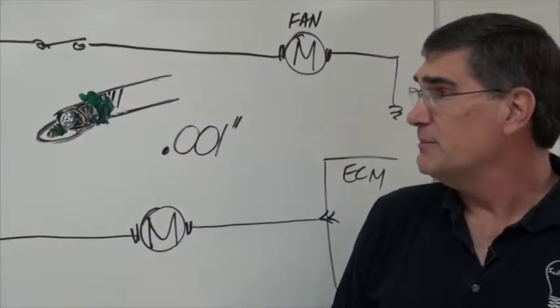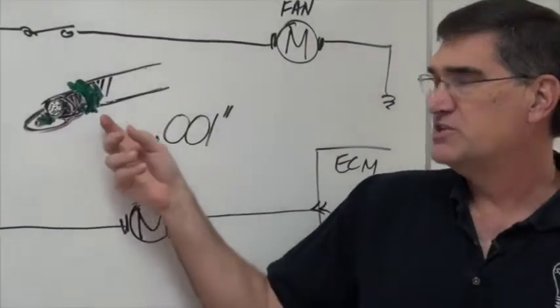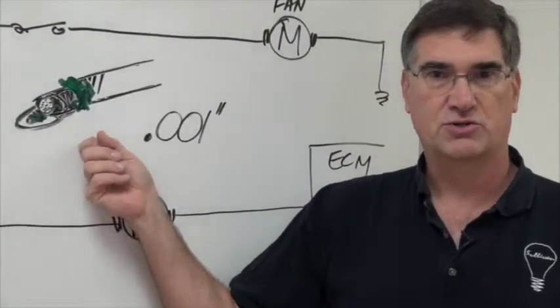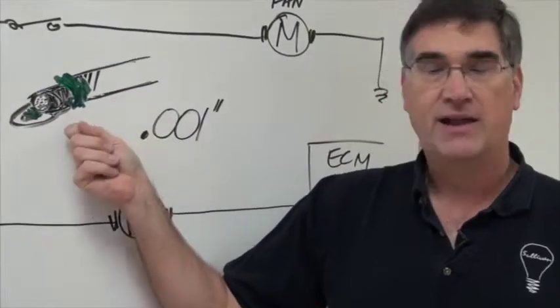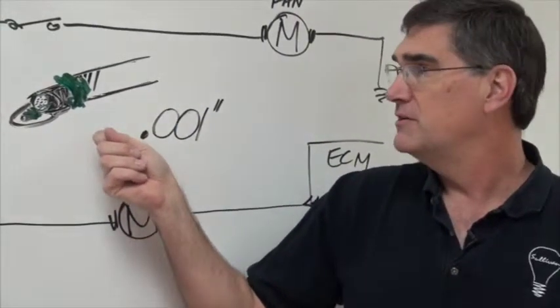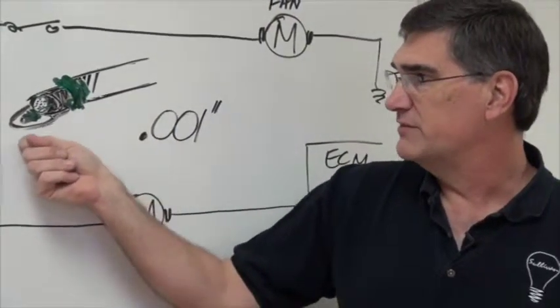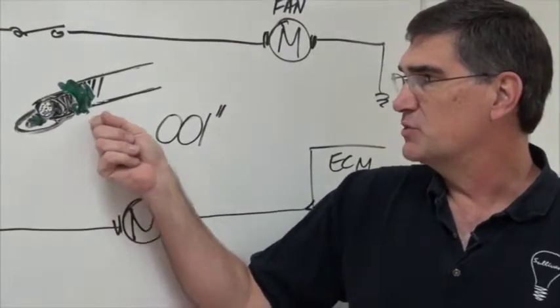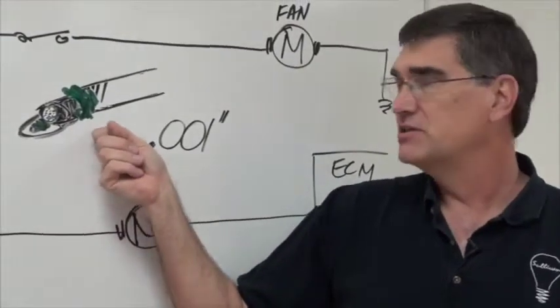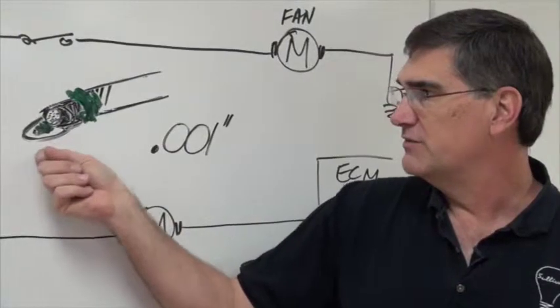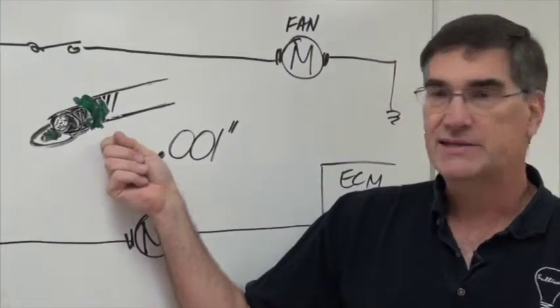The problems with corrosion will almost always occur at the end of the wire because that's where the dissimilar metal corrosion occurs, because you've got copper wire and not copper terminals. This is where the greatest amount of environmental exposure is, where the greatest amount of mechanic damage is, and where the greatest amount of corrosion will occur.